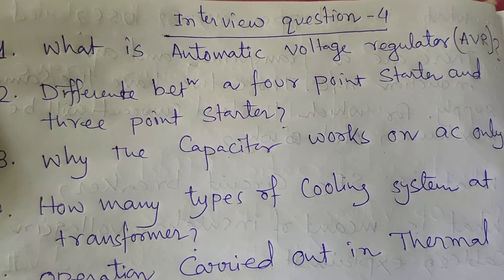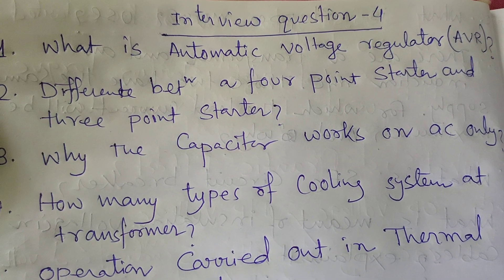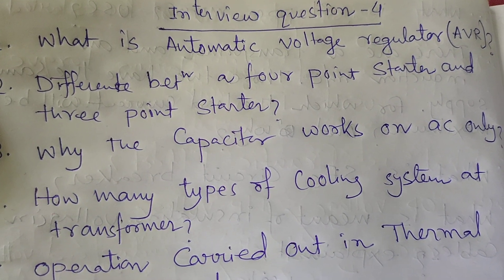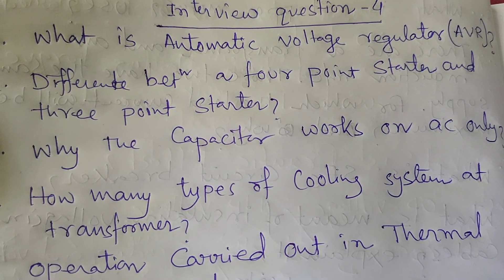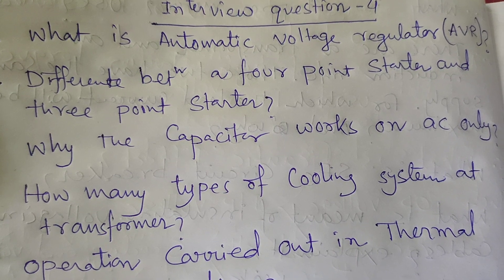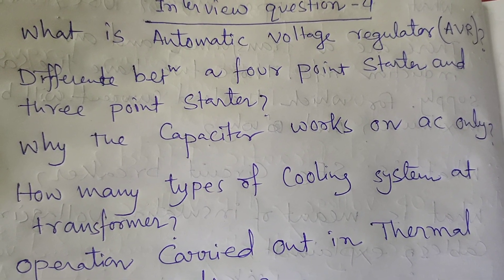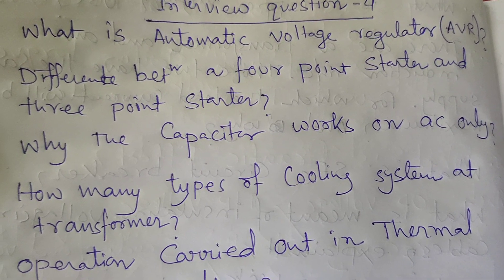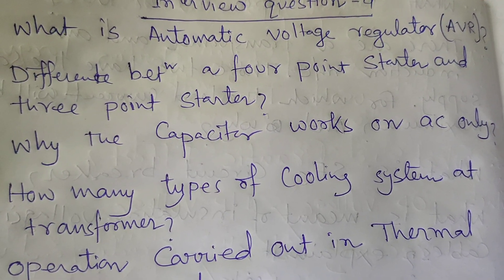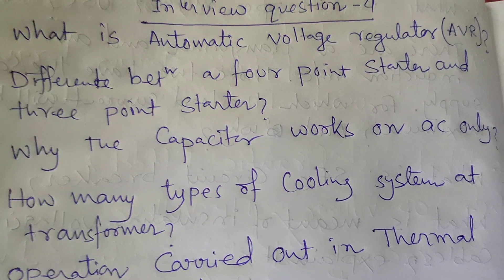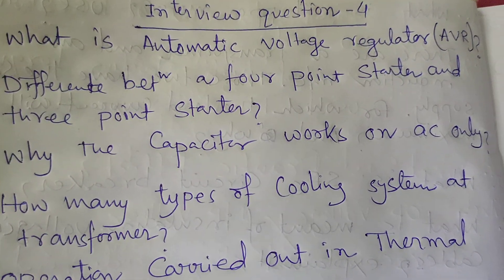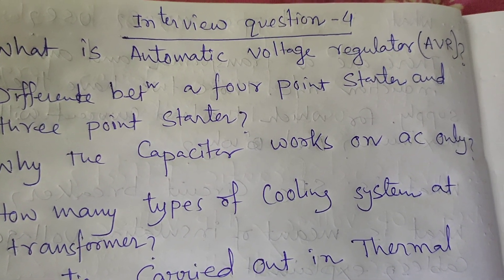First question: What is automatic voltage regulator? AVR is an abbreviation for automatic voltage regulator. It is an important part in synchronous generators. It controls the output voltage of the generator by controlling its excitation current, thus it can control the output reactive power of the generator.